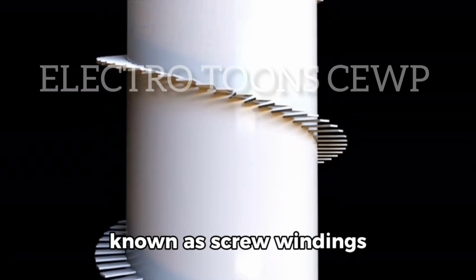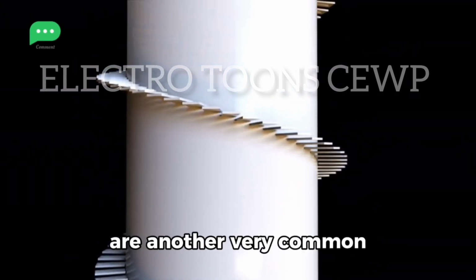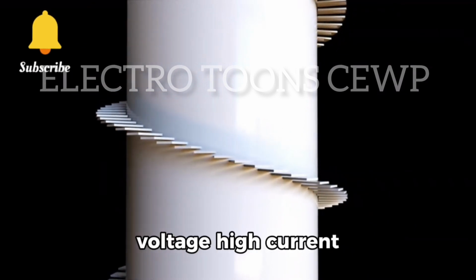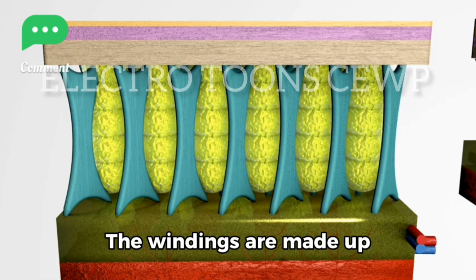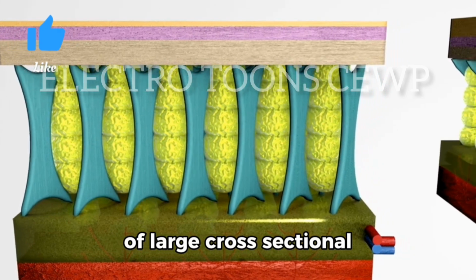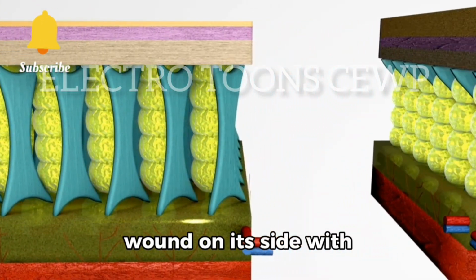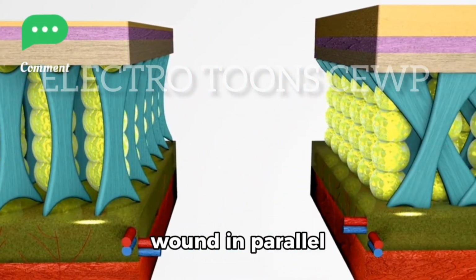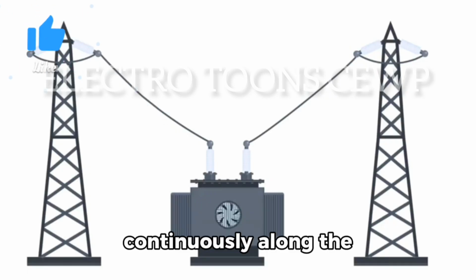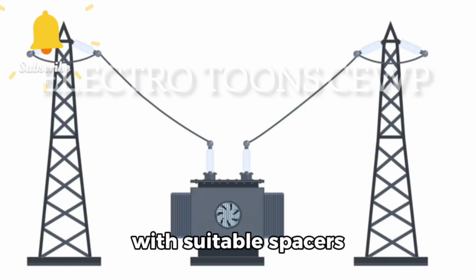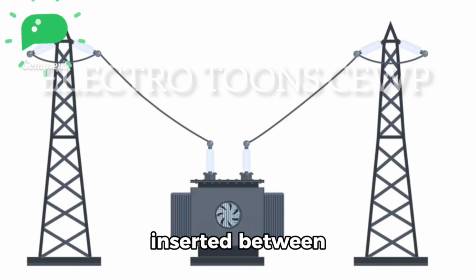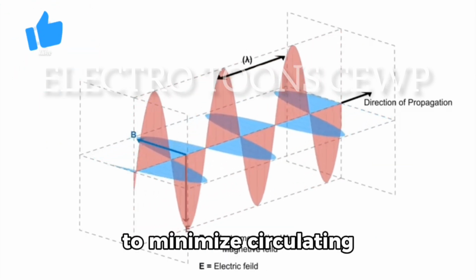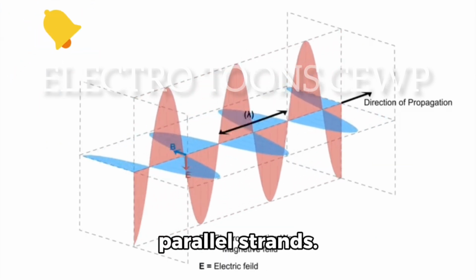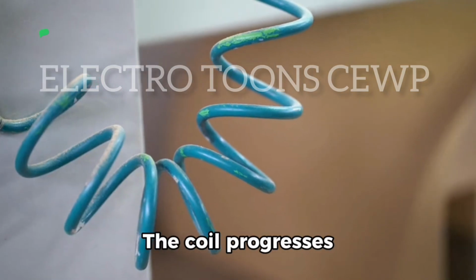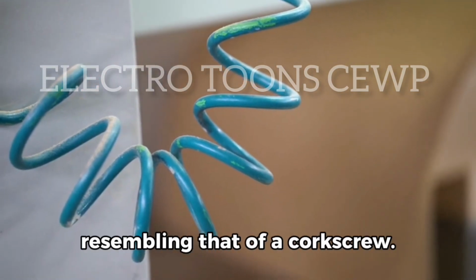Helical windings, also known as screw windings, are another very common cylindrical coil arrangement used in low-voltage, high-current transformer applications. The windings are made up of large cross-sectional rectangular conductors wound on its side, with the insulated strands wound in parallel continuously along the length of the cylinder, with suitable spacers inserted between adjacent turns or discs to minimize circulating currents between the parallel strands. The coil progresses outwards as a helix resembling that of a corkscrew.